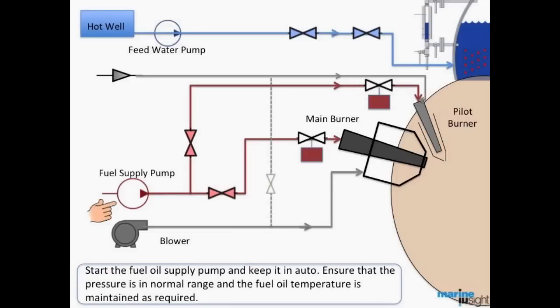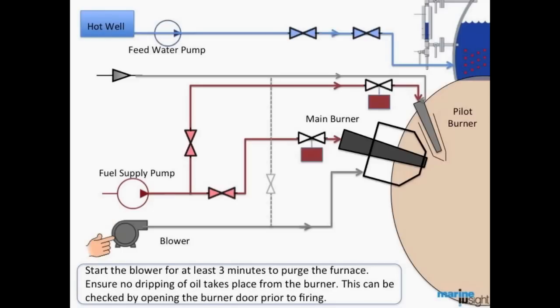Start the fuel oil supply pump and keep it in auto. Ensure that the pressure is in normal range and the fuel oil temperature is maintained as required. Start the blower for at least three minutes to purge the furnace.